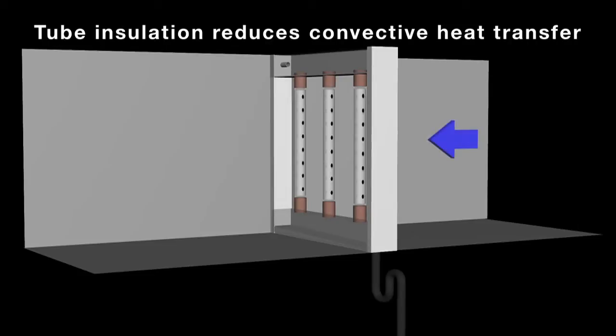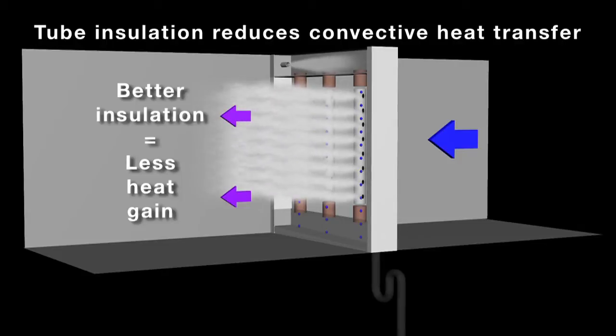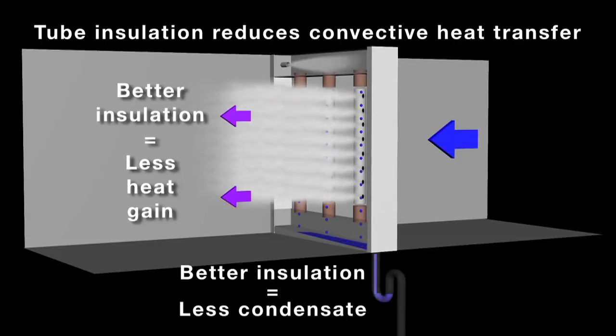Dispersion tube insulation reduces convective heat transfer, thereby reducing condensate production and downstream air heat gain. The better the insulation, the less condensate produced and heat transferred. Note that dispersion tube insulation only reduces convective heat transfer. It does not reduce downstream heat gain caused by the sensible heat of steam dispersed into the air stream.